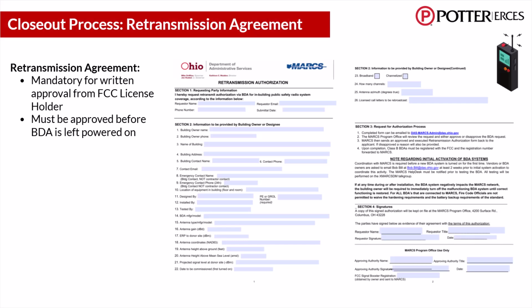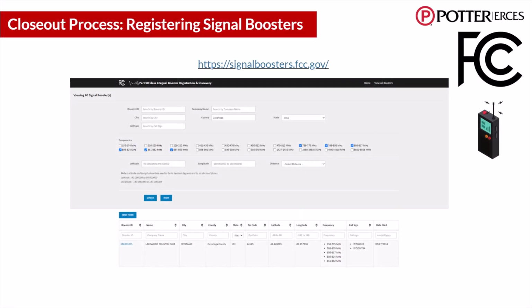A retransmission agreement will be required from the FCC license holder and must be attained before the BDA is allowed to continue operation. Much like an elevator certificate, the retransmission agreement is often a 5-year agreement and must be renewed before it expires. All Class B ERCESs must be registered with the FCC prior to operation. This is not approval, simply a registration so the FCC knows where BDAs are located in case noise is reported. This helps the FCC licensee identify BDAs potentially causing the noise issues.